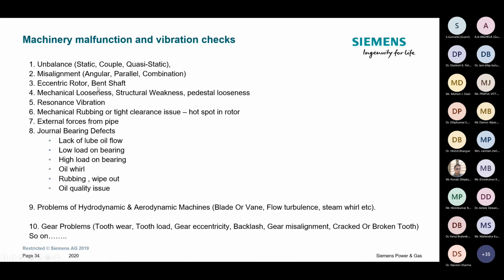A bent shaft could also be a permanent bend. What is happening is that in many old power plants, the material is chrome-vanadium based creep-resistant material. They are supposed to withstand this high temperature, but over a period of time their grain boundaries start dislocating because of the creep effect. So they start to permanently bend, and I'm talking about a very nominal bend, and this nominal bend also causes 0.1, 0.2 millimeter vibration as a result.